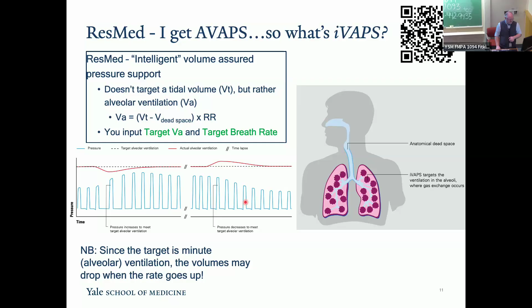Since the target is a minute ventilation rate, not a specific target for tidal volume, if the patient's rate is increasing on the machine, it's going to be dropping the tidal volume in order to maintain minute ventilation. So unfortunately, in this case, intelligent maybe is overthinking it and causing problems. So just be aware that's actually one of the deficits of this iVAPS mode.